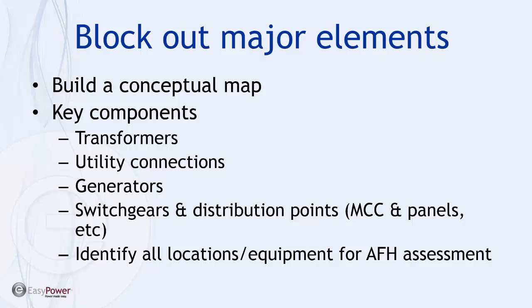As you identify pieces of your one-line, whether you know how they're connected or not, you more than likely know where they're located in your plant. These key components include transformers, utility connections, generators, all of the switchgear and distribution points including motor control centers and panels, and any type of ATSs or switching locations. You want to identify all of these as the equipment for arc flash hazard assessment.